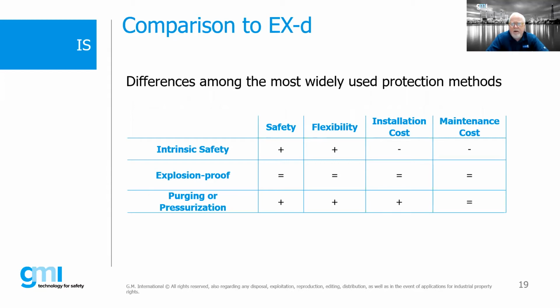Flexibility - intrinsic safety offers a lot of flexibility. Again, installation costs and maintenance costs on IS are actually extremely nice. One of the big benefits of intrinsic safety is that, per the standards, you can actually do a lot of your maintenance on intrinsic safety loops while they're energized, or live. Some clients will say no, we don't allow that, but the standards actually do allow you to do a lot of maintenance on intrinsic safety while it's live.